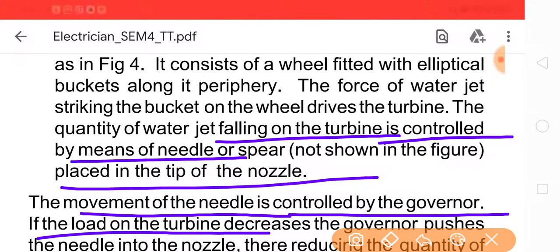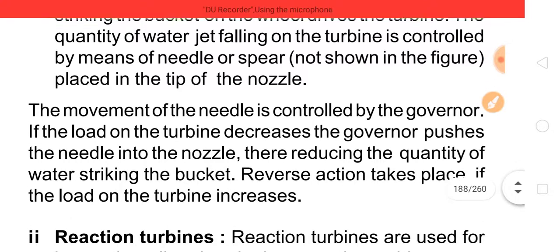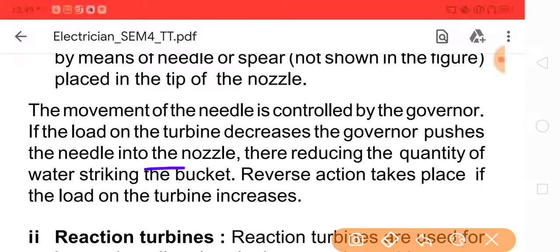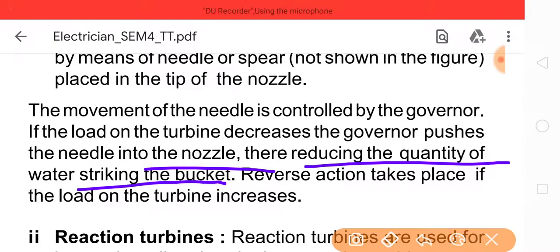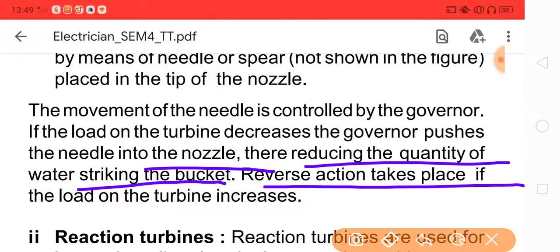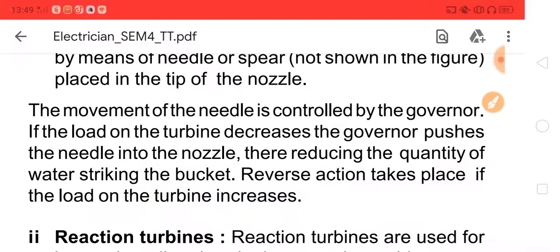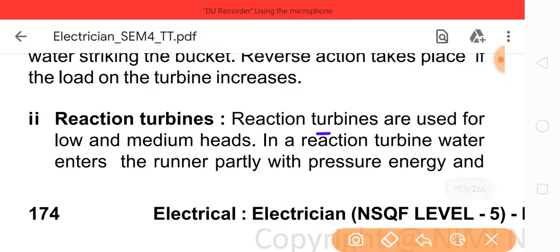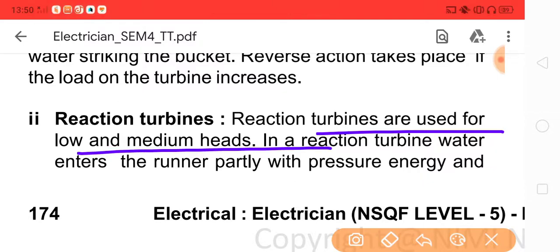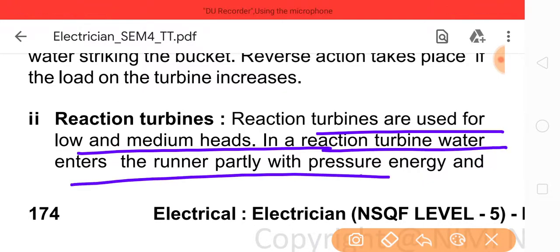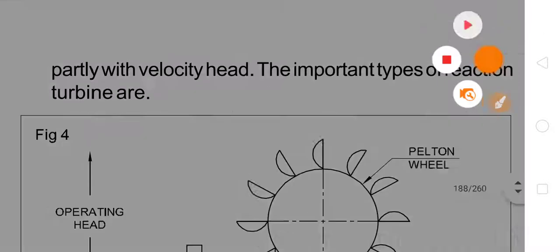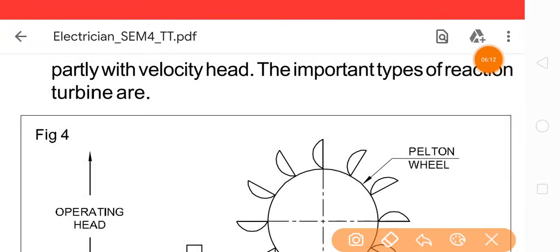If the load on the turbine decreases, the governor pushes the needle into the nozzle, thereby reducing the quantity of water striking the buckets. Reverse action takes place if the load on the turbine increases. Reaction turbine. Reaction turbines are used for low and medium heads. In a reaction turbine, water enters the runner partly with pressure energy and partly with velocity head.